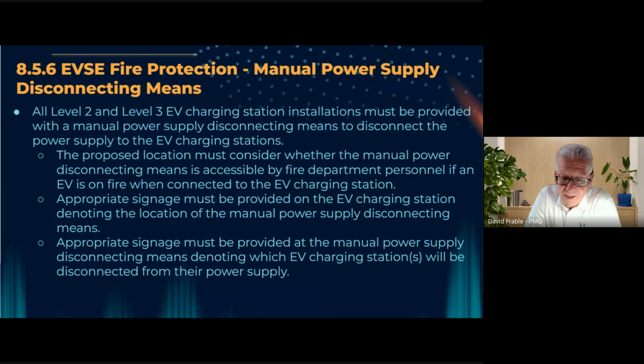Signage is required at the EV charging station to inform the responding fire department personnel and others where the manual power disconnecting means is located. And also signage is required at the disconnecting means to inform the responding fire department personnel and others which EV charging station will be disconnected from the power supply.